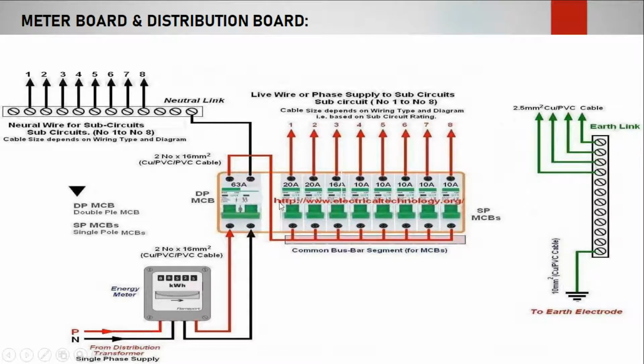From this DPMCB, one wire is neutral, the other is phase. All phases are connected to the respective switches, whether lighting switch or AEH switch. The neutral is made common, and one phase goes to all the switches. In any switch there is no neutral, only phase runs, because switching on and off breaks or connects the phase. When you switch on, it connects and the common neutral acts. When you switch off, the electrical supply disconnects.